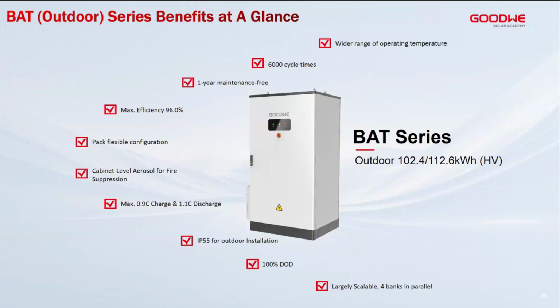install it outside. 100% DOD, and in terms of scaling up, instead of doing 6 like we did with the BAT indoor, the outdoor version you can do parallel up to 4 banks or towers or cabinets to 1 inverter. So that's how scalable the BAT outdoor is.